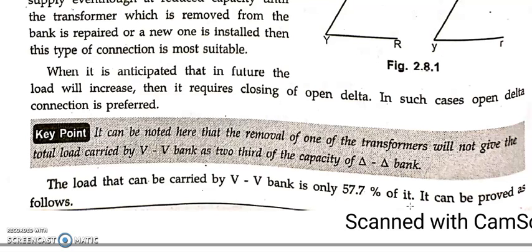Okay, like if you are having a 1 kVA transformer, then it will be 57.7% of 1 plus 1 plus 1, that is totally 3 transformers, right? Because 3 transformers will make a delta connection, but since you are using VV connection, you have to make use of only 57.7% of the total kVA. Total kVA is how much? If each of the 3 transformers has a rating of 1 kVA, then it will be 3 kVA, right? So 57.7% of 3 kVA is your total kVA available from the transformer. Let us see how this 57.7% has come.